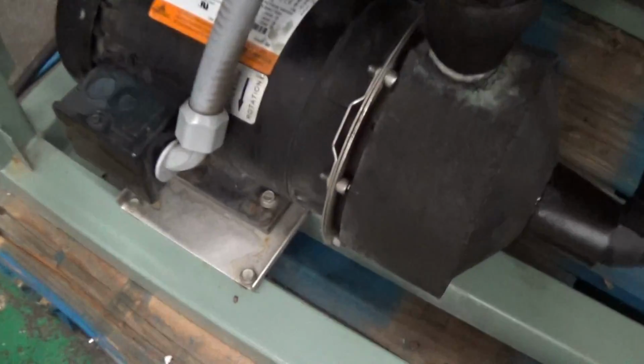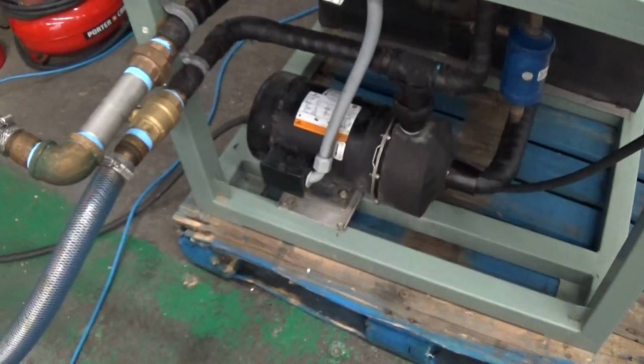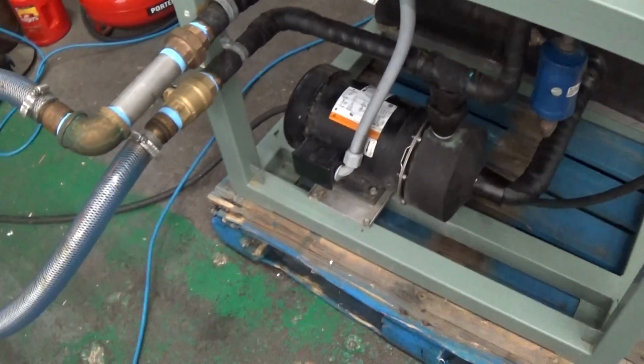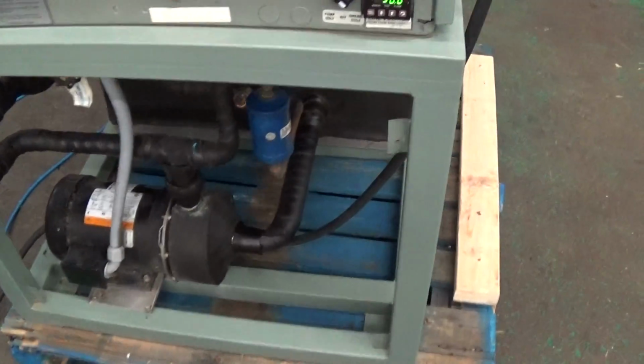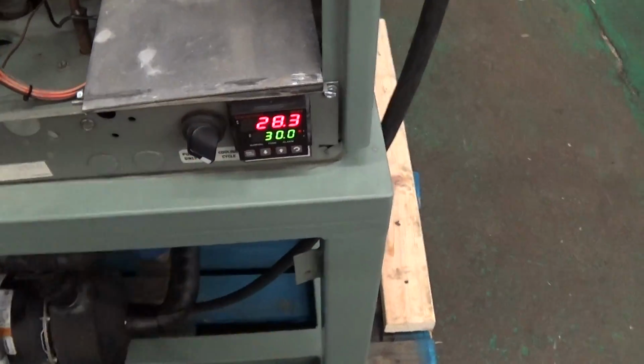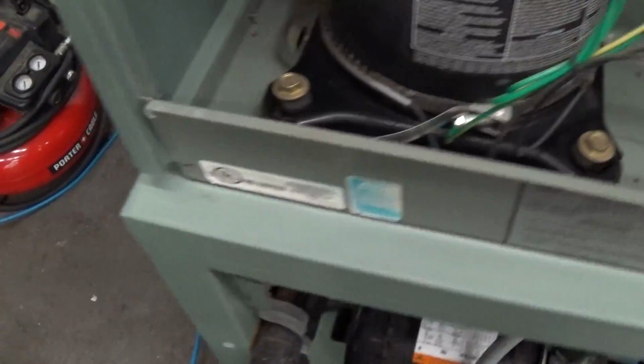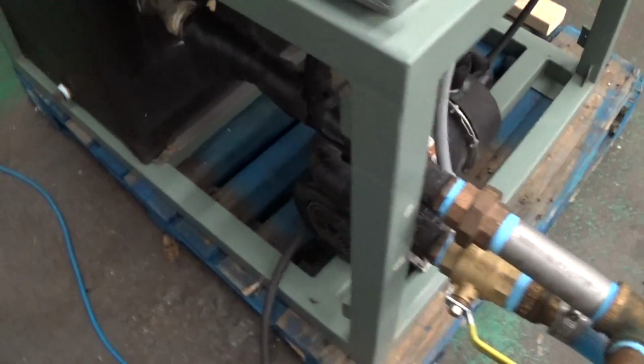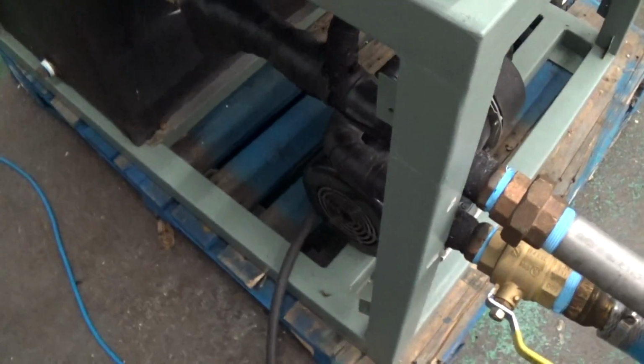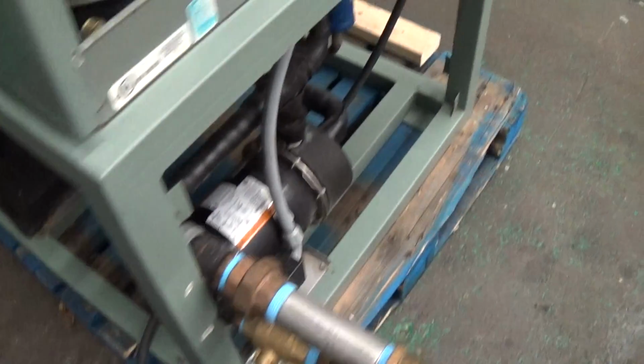So you can see right here is an arrow that says rotation. After you get your three-phase power connected, first thing you do is you get a helper, or you can actually probably reach here if you're doing it by yourself, and you just bump the pump on and off. I'm going to digress for a second.